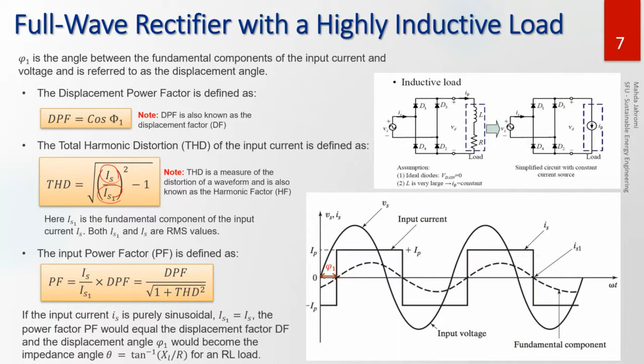Now, if we didn't have a pulse wave, if the current was sinusoidal, the THD would have been 0—you wouldn't have any harmonic distortion, and IS1 and IS would have been the same. In that case, the displacement power factor and the power factor would have been the same.